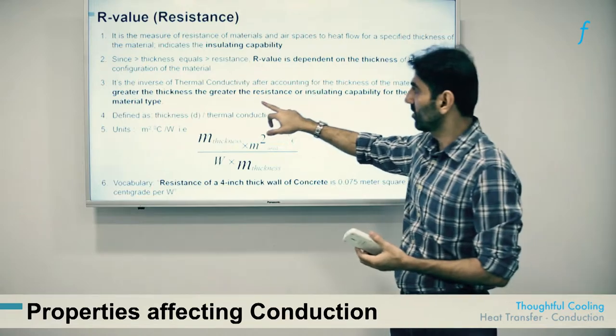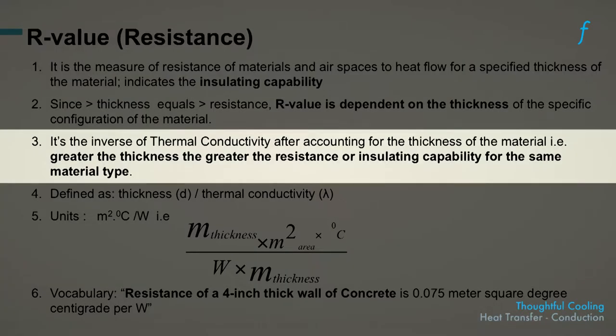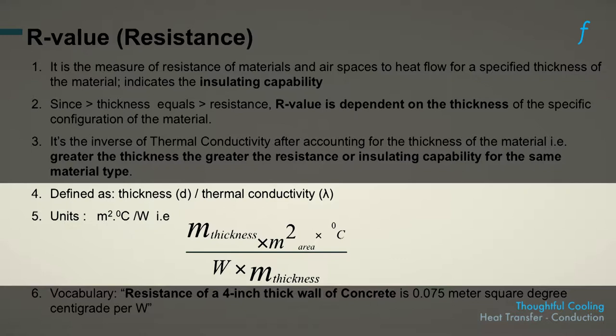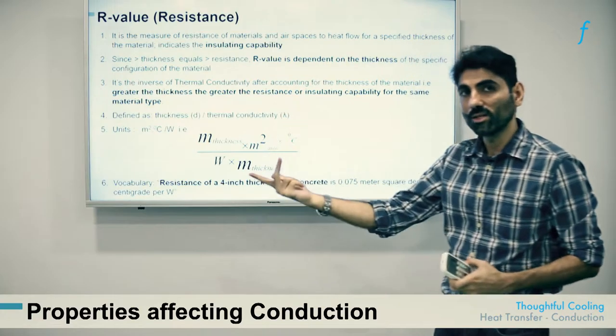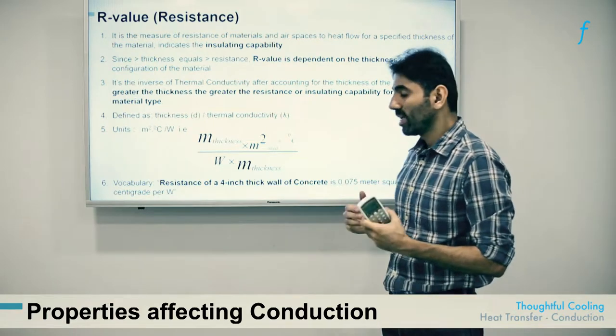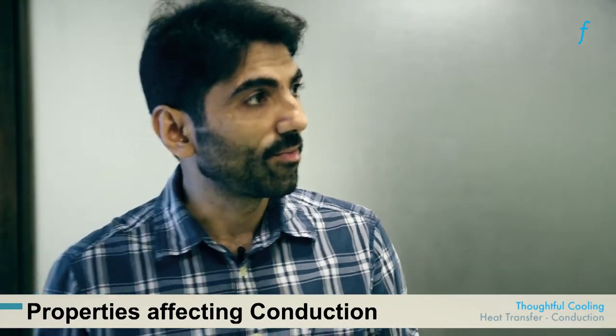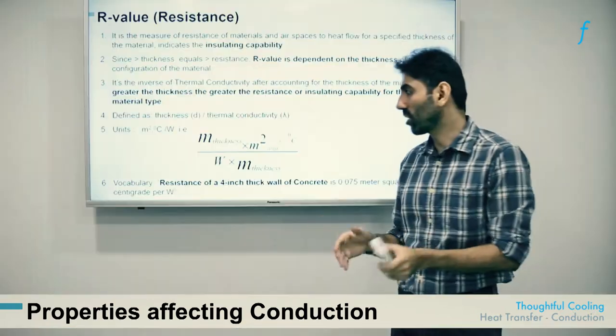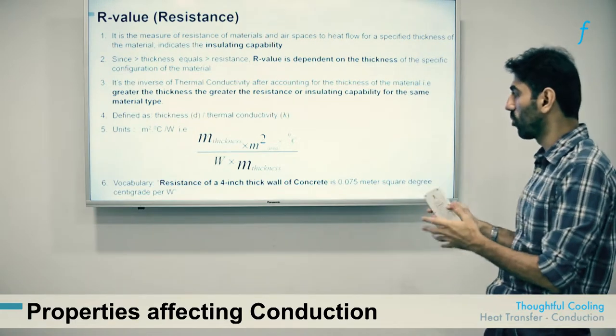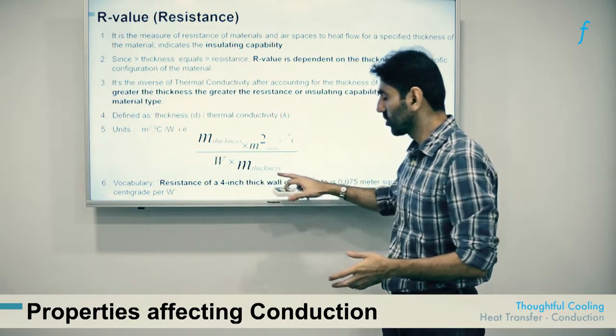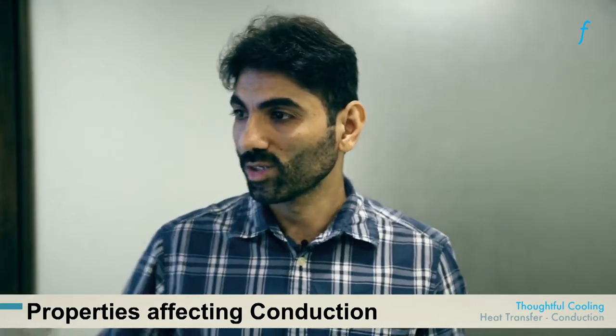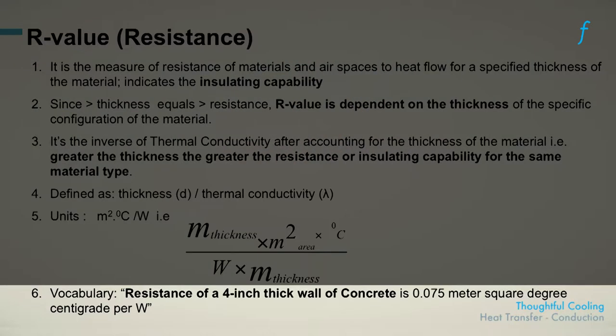Resistance is the inverse of thermal conductivity after accounting for the thickness of the material — the greater the thickness, the greater the resistance. It is classically defined as the thickness of the material divided by the thermal conductivity, and the units are the inverse of those used for thermal conductivity. In practice, resistance is conveyed by including the thickness: for example, the resistance of a 4-inch thick wall of concrete is 0.075 meter square degree centigrade per watt.